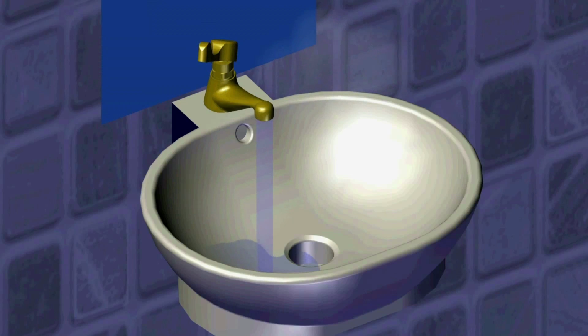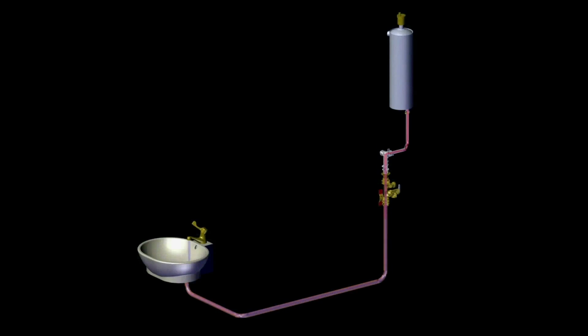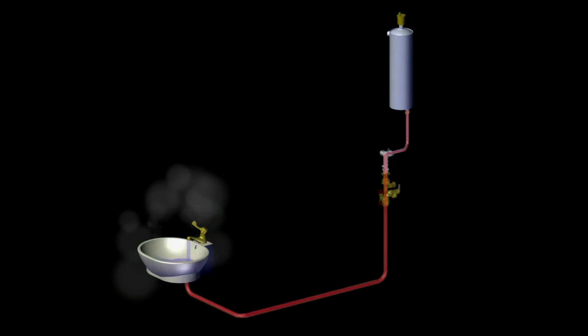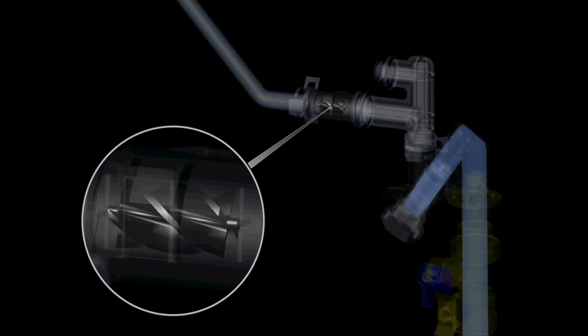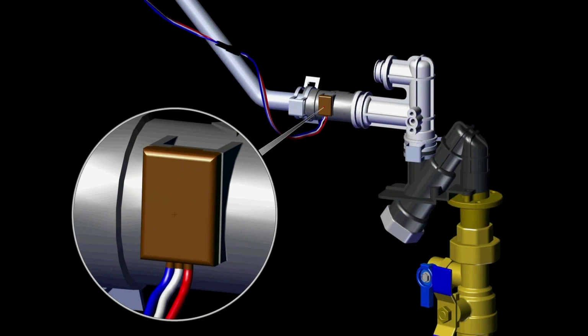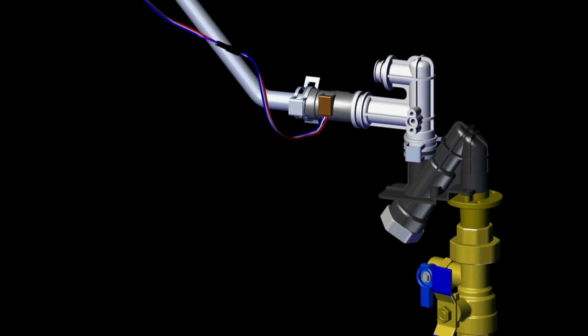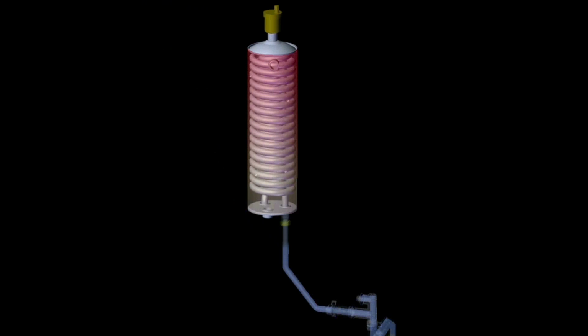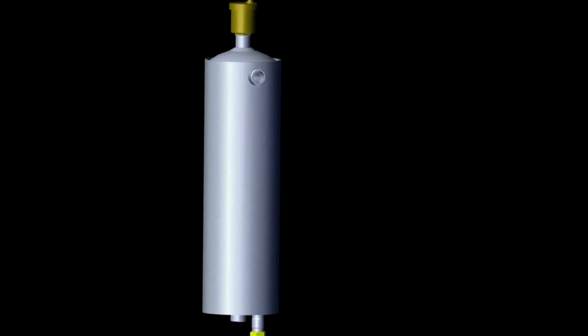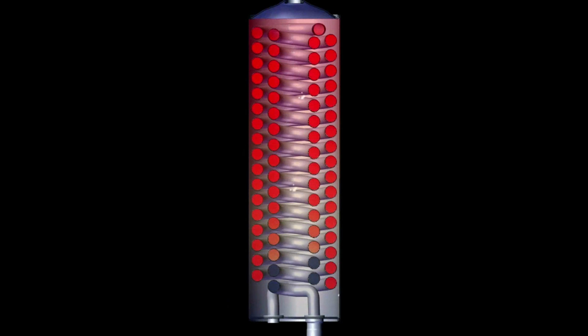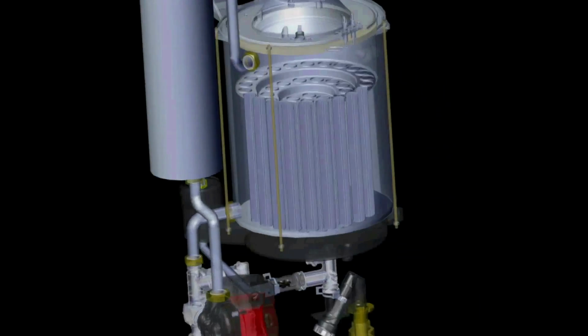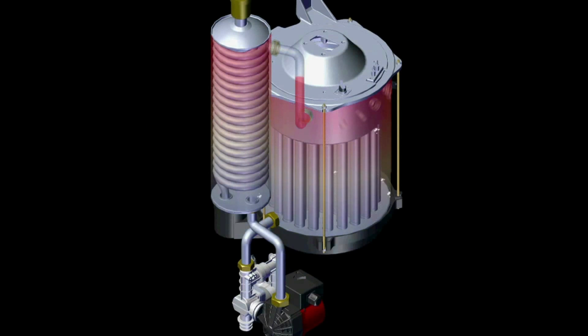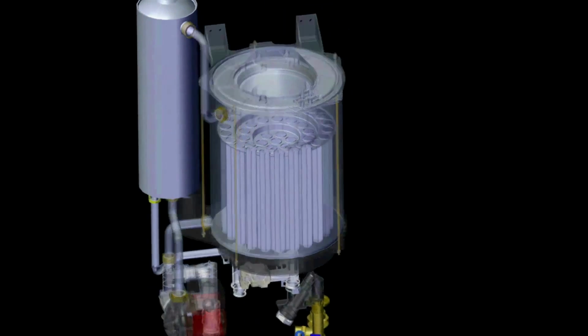During central heating mode, central heating is temporarily stopped by the movement of the three-way valve to divert the heated water to circulate back through the internal storage tank, providing priority and large amounts of domestic hot water production. When the consumer uses domestic hot water, direct city water would enter into the domestic hot water heat exchanger, which is detected by the flow sensor. Hot water is created after heat exchange between hot heated water outside the coil and cold water inside the coil. Domestic water is heated inside the highly efficient heat exchanger located inside the internal storage tank, as heated water passes through the tank, producing large amounts of domestic hot water.